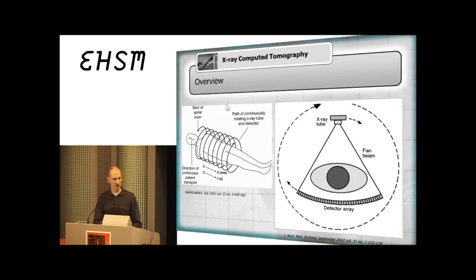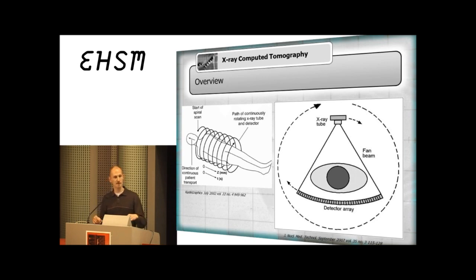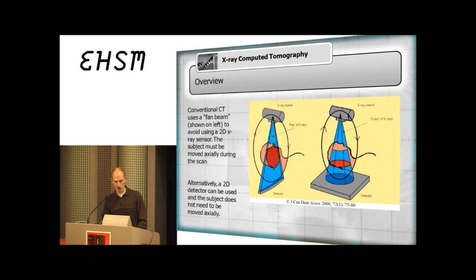Commercial CT scanners scan in a helix — you're on a bed rolling through the scanner while it constantly spins, using a fan beam with a one-dimensional detector array. An easier method is cone beam CT: instead of a fan beam with a 1D detector, you use a cone beam from a standard x-ray tube onto a two-dimensional detector, getting a nice image that's much easier to process.